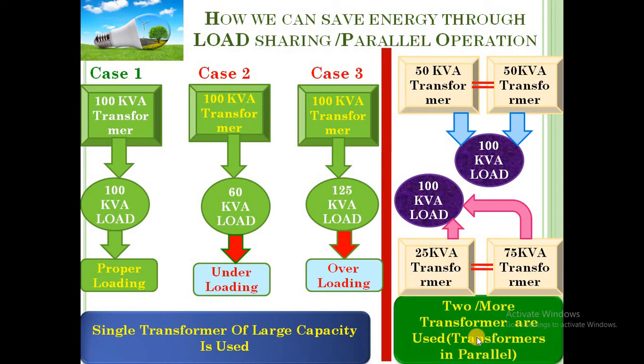So two or more transformers are used in parallel to share a common load. Suppose a transformer has to undergo maintenance, transformer चा maintenance करायचा असेल, then we can take out one transformer and the remaining load can be shared by the other transformers which run in parallel. If some fault occurs in one transformer, suppose here a fault occurs on the 25 kVA transformer, then this transformer will completely shut down and we have to supply the 100 kVA load by the 75 kVA transformer, and also we can connect another transformer in parallel with this 75 kVA to supply the 100 kVA load. So in this way we can save energy, and we can avoid underloading and overloading conditions of a transformer if we connect two or more transformers in parallel.